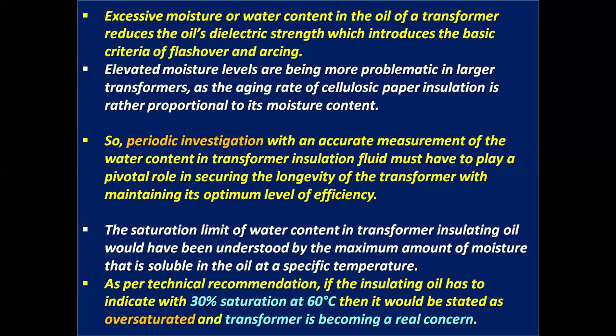The saturation limit of water content in transformer insulating oil is understood as the maximum amount of moisture that is soluble in the oil at a specific temperature. As per technical recommendation, if the insulating oil indicates 30% saturation at 60 degrees centigrade, then it would be stated as oversaturated and the transformer becomes a real concern.